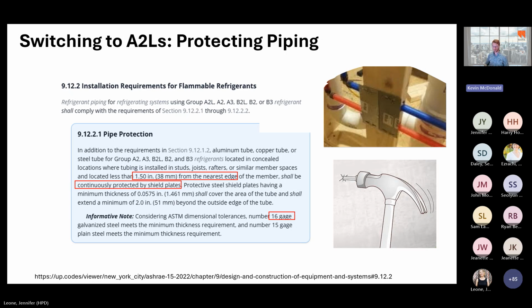one of the first, more simple considerations is you have to protect the piping. This has always been best practice, even with R410-A refrigerants. The pipes in the picture on the right here are water piping, but the same concept would apply if that was refrigerant piping. If someone can put a nail through it through the wall, obviously that's bad. We'd leak a lot of refrigerant. So there are some protections that are required. Generally, you're bracing and holding the refrigerant piping more than 1.5 inches, probably best to specify 2 inches for buffer, away from the drywall or sides of a shaft or any sort of location behind a wall, or you're adding 16 gauge steel to protect it. There's a link down below when these slides get sent around where you can read the more specific code requirements here. If you go to the next slide, please, Jen.